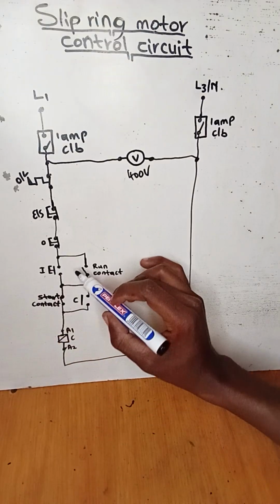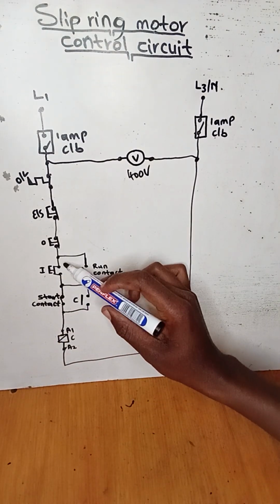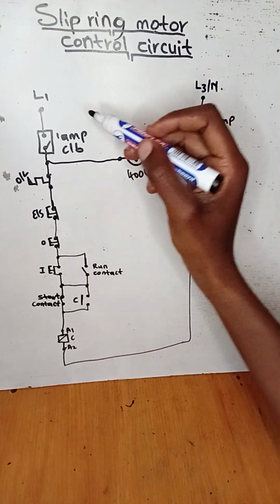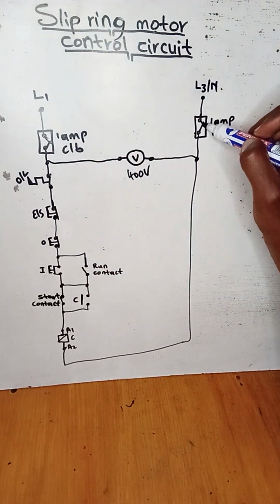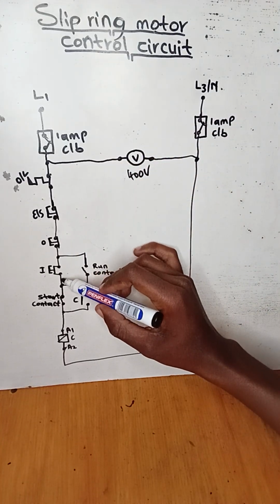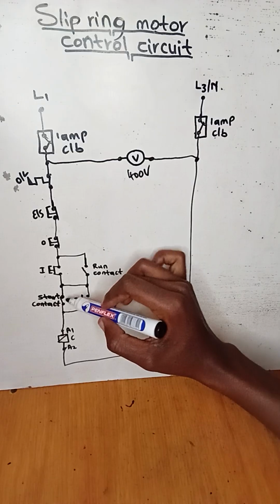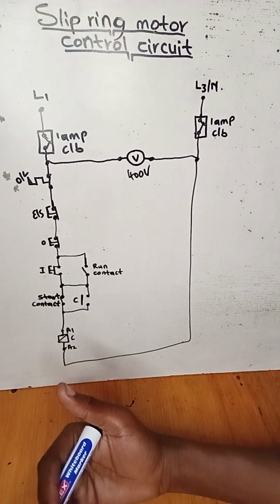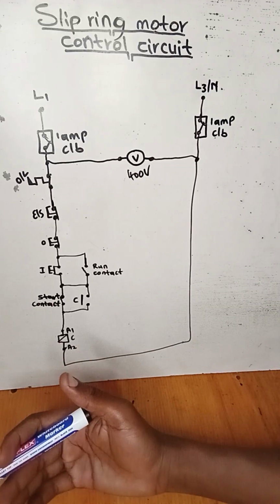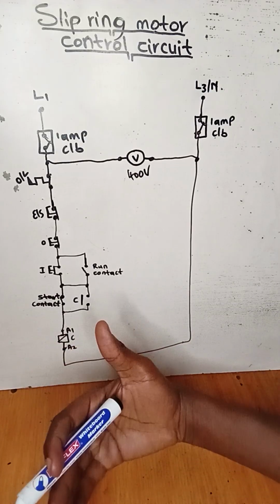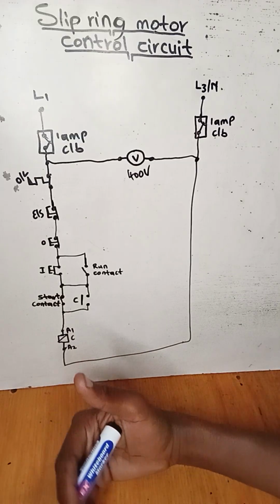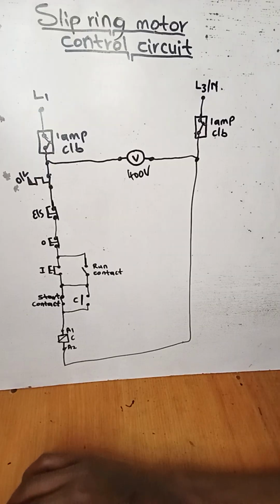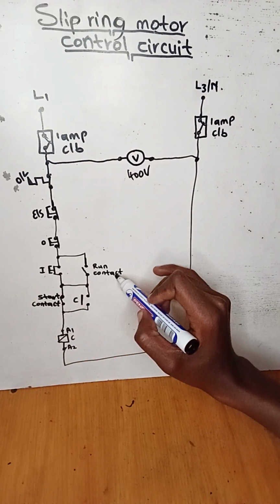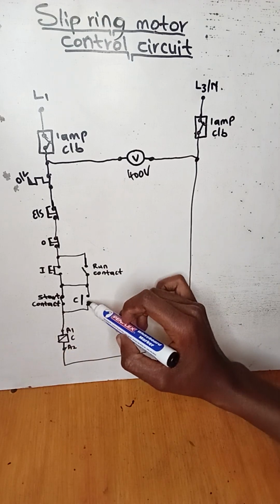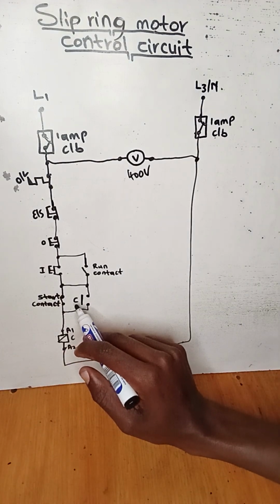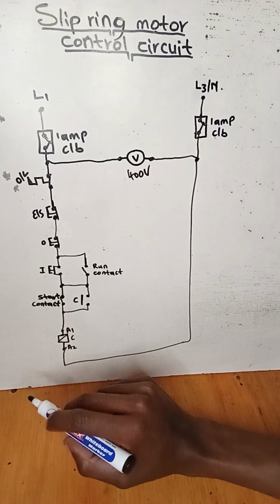So this is what will happen when we press the start button. It will create a closed contact and current will flow. Okay, switch on your 1 amp circuit breakers, press the start button, current will flow and find the closed contact of the start contact. So the start contact must help our coil to be energized, and our run contact is the one that will help our coil to keep on running, right? The run contact will help our coil to keep on running along with the retainer of the contactor, right?